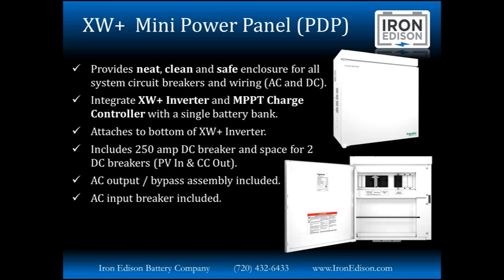This XW Plus mini power panel connects to a single XW Plus inverter. It connects right down below at the bottom of the inverter. It includes one 250 amp DC disconnect, as well as the places to land the battery positive and battery negative cables. There's also bus bars and labeling and all the wiring to land the AC input and output, and the wires to connect from the power panel to the inverter. The AC output and bypass assembly is included, and the AC input breaker is included.